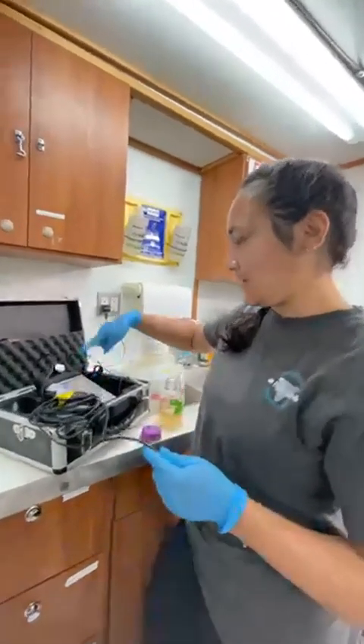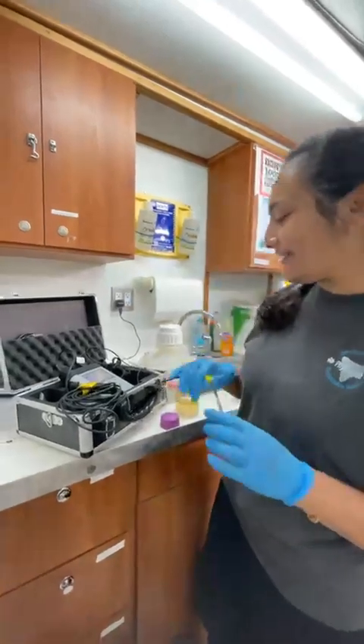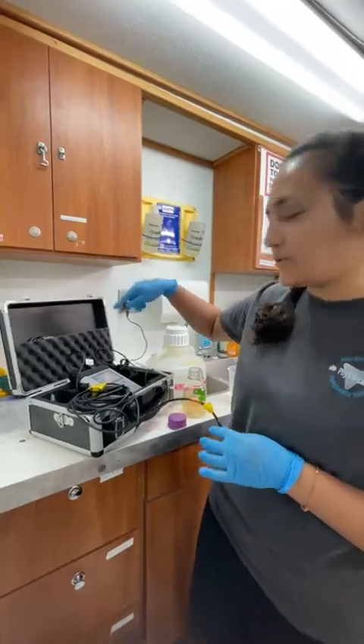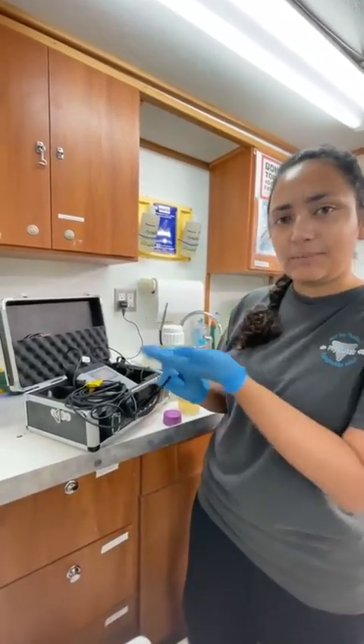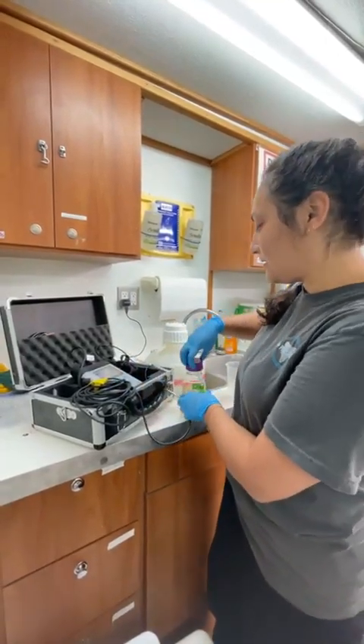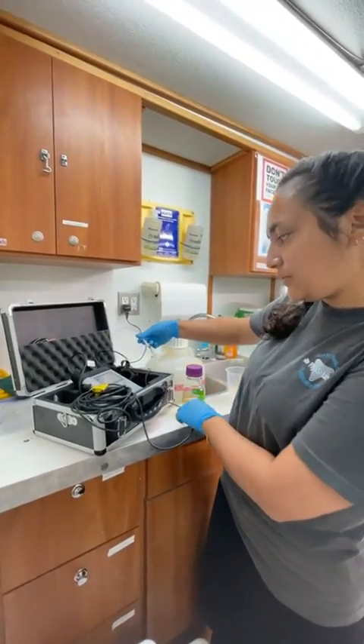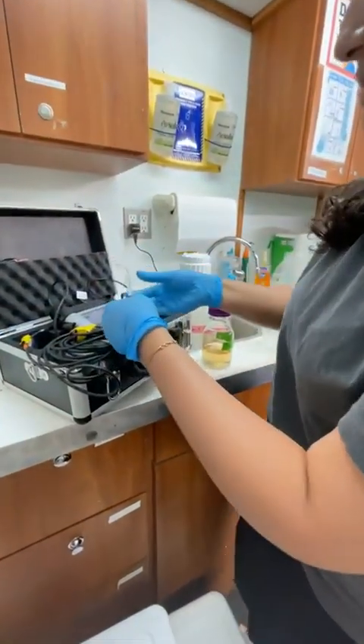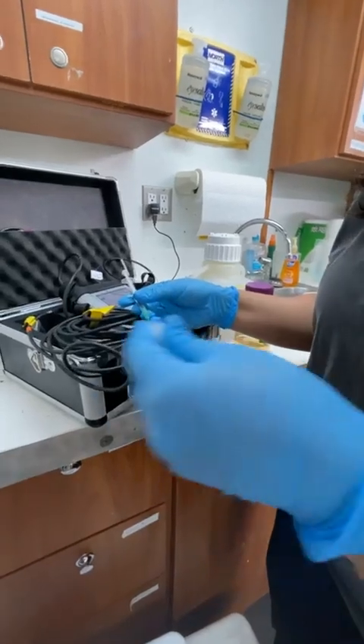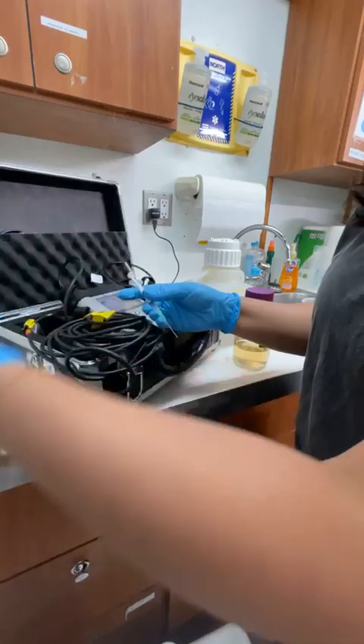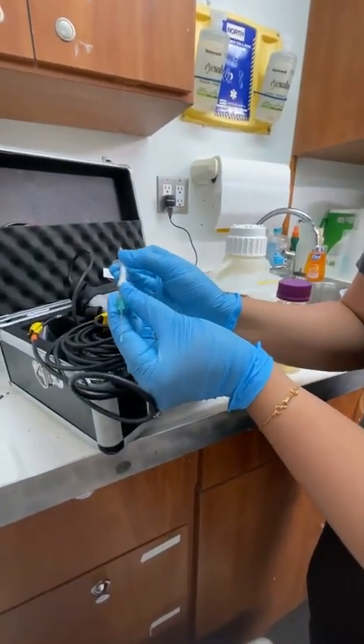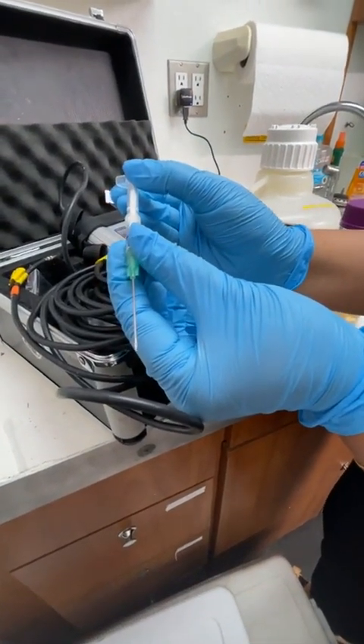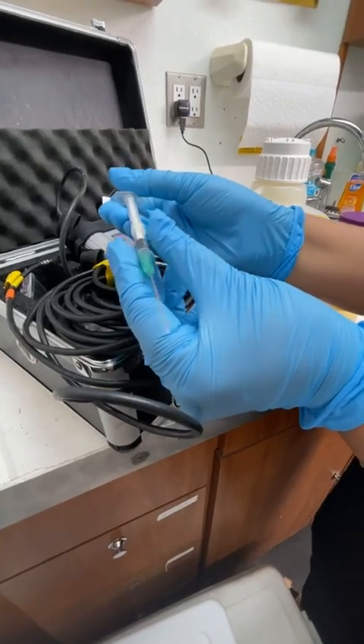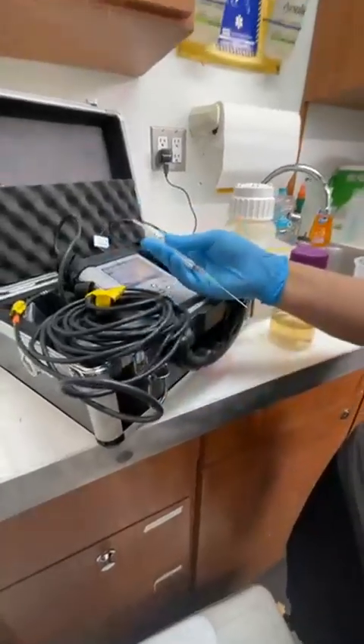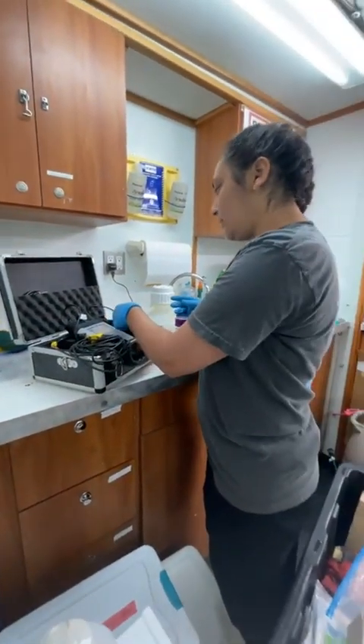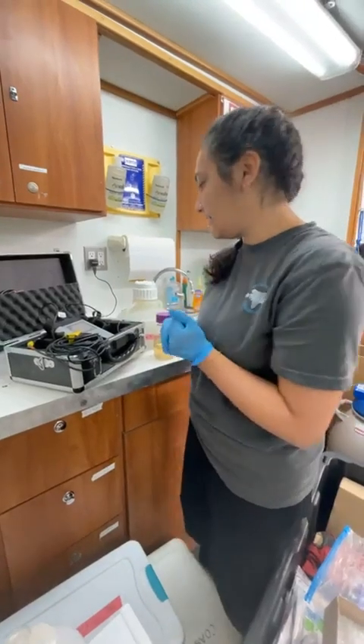Yeah, so this is the machine that senses both oxygen and temperature. So this is the temperature probe. So right now I'm calibrating, and then this is the oxygen probe. It has a needle with a fiber optic cable inside of it. You should be able to see it flash red, hopefully. But it is a very delicate cable, and it senses the oxygen in liquid, and then we're also using it in sediments that we're collecting.